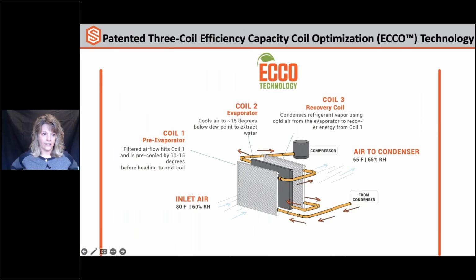So what is this ECCO technology? And this patented 3-coil optimization technology. And I'm going to minimize this here so I can walk you through this, because it is very exciting and very interesting, but there are 2 different ways to look at this. We have the way that the air is flowing through these different coils, and then we have what's going on with the refrigeration. So the air coming in is hitting coil number 1. Now, for those of you who are familiar with our heat exchanger technology that we have on our XT units, which are big units, but they're very energy efficient, remove a lot of water, and very effective. This is pretty much what you're getting, but in a more compact footprint.